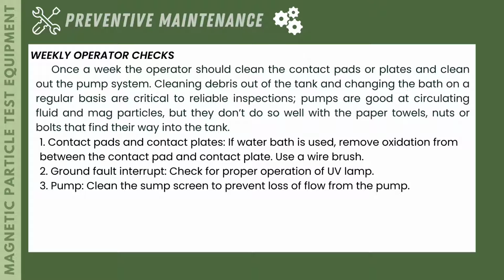First is the contact pads and contact plates. If water bath is used, remove oxidation from between the contact pad and contact plate. Use a wire brush if needed. Second is the ground fault interrupt. Check for proper operation of UV lamp. Lastly, the pump. Clean the sump screen to prevent loss of flow from the pump.